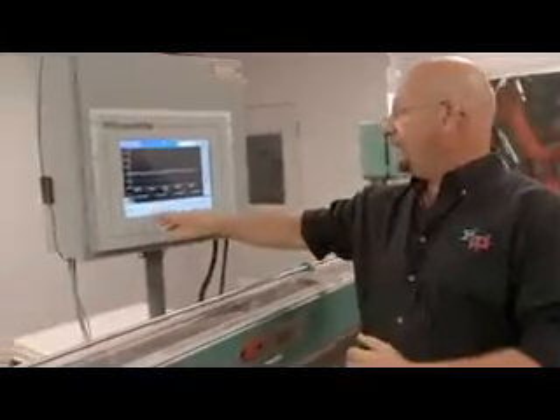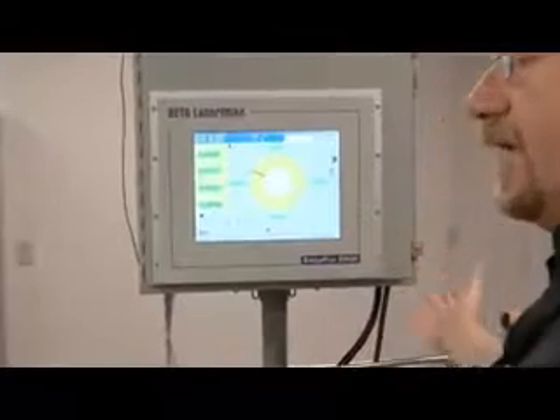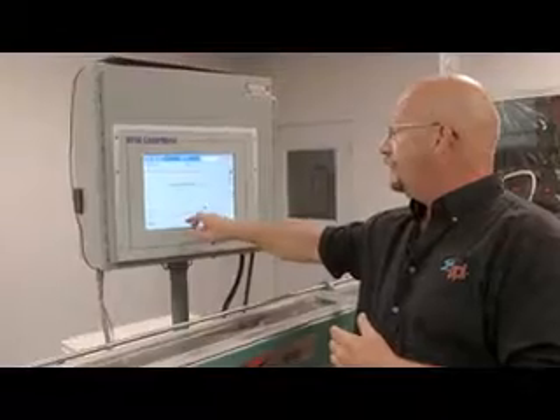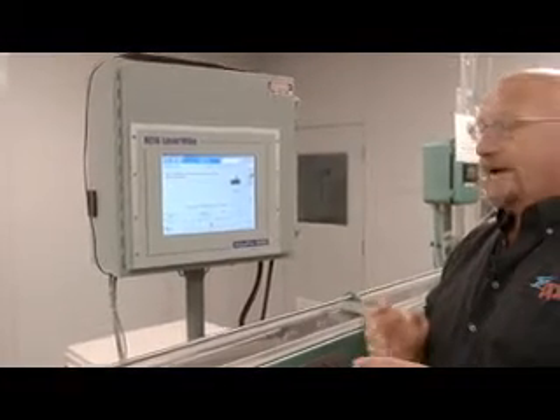When we set up the Beta LaserMike, we will go ahead and get the line running. What we're doing is basically setting up calibration for the ultrasonic. We'll take a snapshot of the product, grab that product, and measure it in four locations.